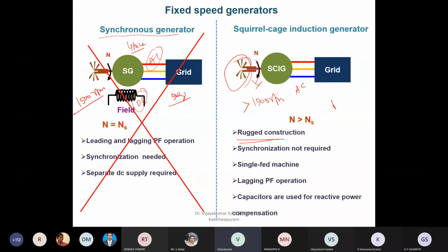It is a single fed machine. Only stator coils are available to access. And another main disadvantage of these squirrel cage machines is lagging power factor operation. Whether it acts as a motor or a generator, it always takes reactive power from the grid. So it always takes reactive power from the grid. So if you consider the point of common coupling, the power factor is lagging. That's the main disadvantage of this generator. This disadvantage we can also eliminate by connecting capacitor banks at the point of common coupling, so that the reactive power requirement of the machine will be provided by these capacitors, and at the point of common coupling we are able to maintain the unity power factor.